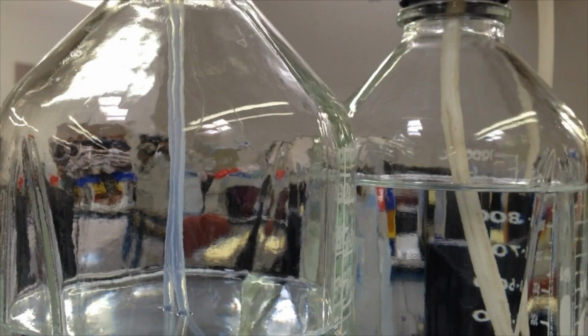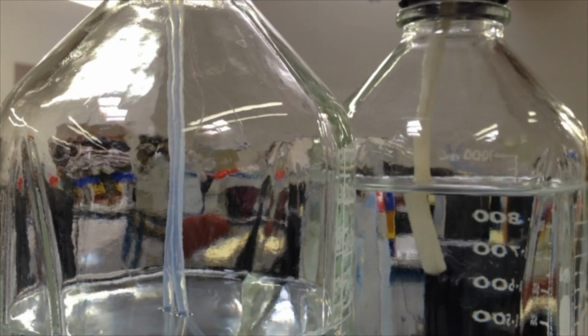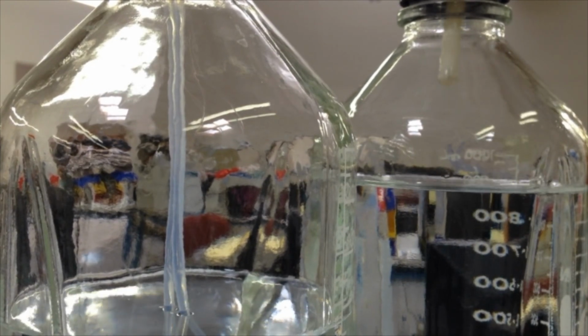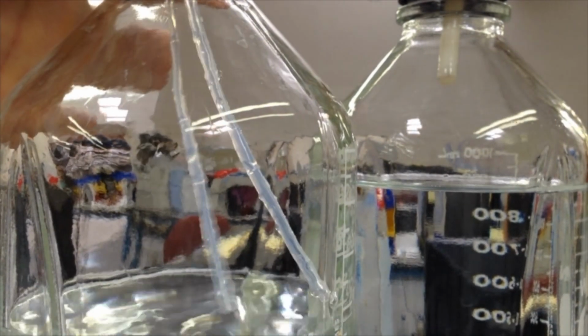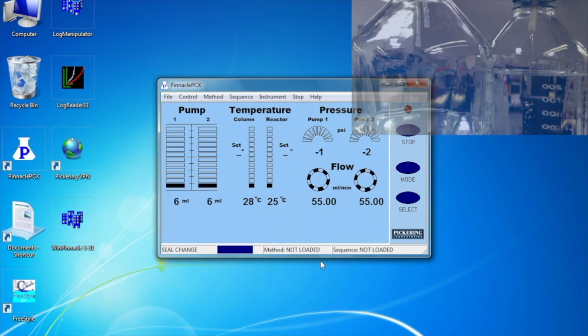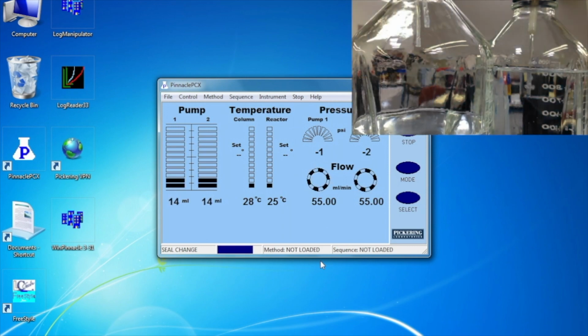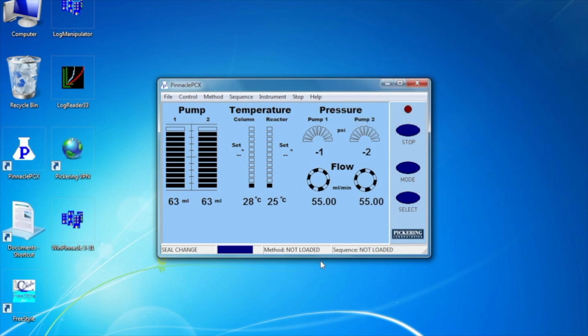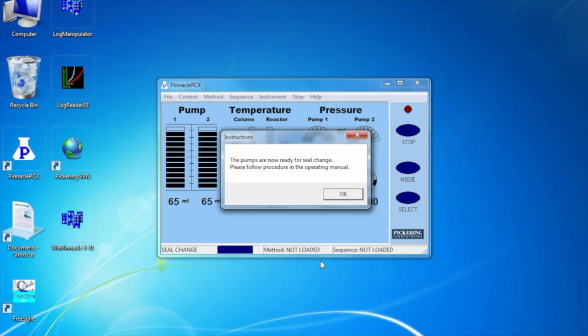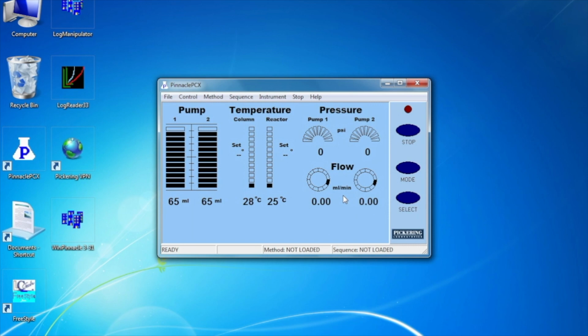Move the piston wash tube and the pump flush tubes to the top of their bottles so they are not submerged in piston wash or pump flush solution. Click Continue after this is done. The pump will fill with air through the pump flush lines, and it will dispense piston wash solution back into the piston wash bottle. The pumps and valves are now ready for seal change.